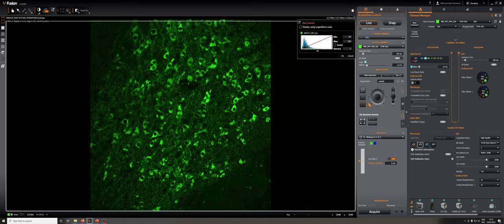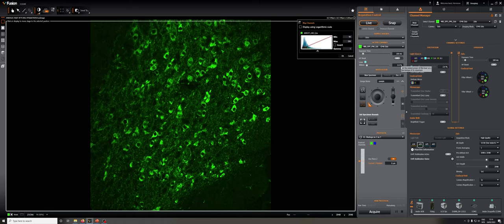So what kind of adjustments can I make? There are two main parameters that we're going to adjust. One is the exposure time, the other is the laser power. If we increase either of those, we'll increase the bleaching. If we increase the exposure time, we will increase how long it takes to acquire an image.